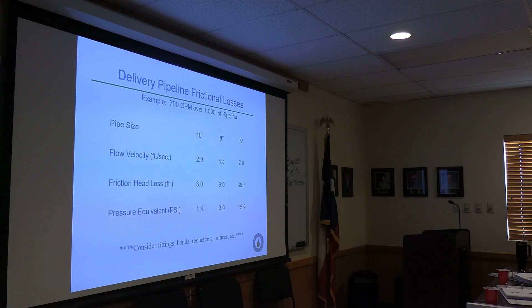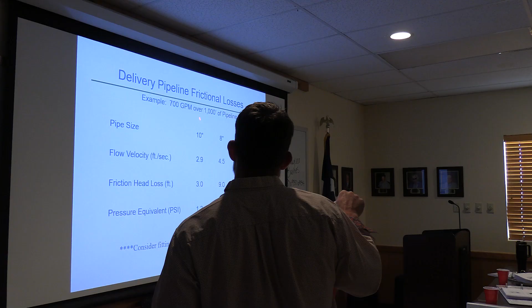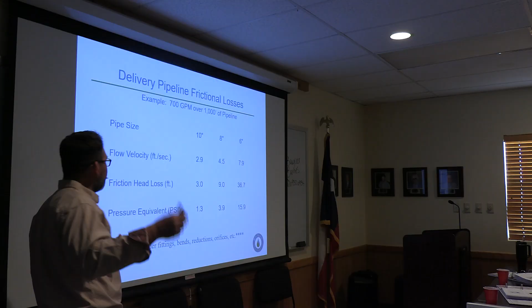The scenario looks something like this. So let's use a pipeline example. You've got 700 gallons per minute that you want to send down 1,000 feet of pipeline. If you want to size that pipe, you would look at a 10-inch pipe, an 8-inch pipe, and a 6-inch pipe. You've got flow velocity, where the standard in these water systems is less than 5 feet per second. So we've now got two pipe sizes that match. We've got a 10-inch and an 8-inch. The 6-inch is just too small for the 700 gallons per minute. The water's moving too fast.